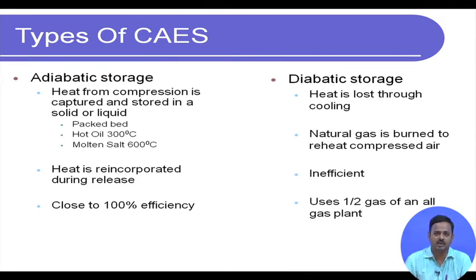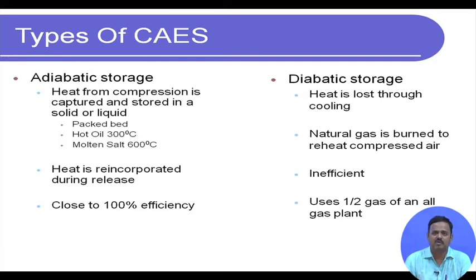Diabatic storage: heat is lost through cooling, and a combustion chamber — typically burning natural gas — is used to reheat the compressed air. It is inefficient, but the amount of natural gas used is still much lower — roughly half or less — than what would be needed to operate a standalone gas turbine plant using natural gas as the combustion fuel.